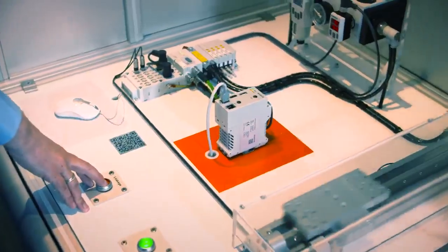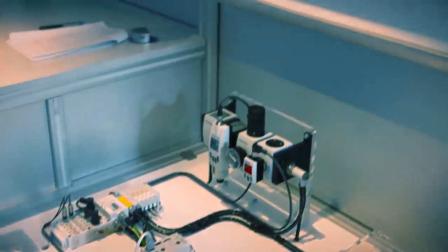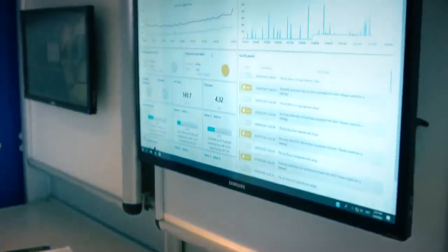If we detect an anomaly in the consumption per working cycle, that usually means that there is a developing leakage, and we can give a notification that this is currently happening, like we can show in our application by creating an artificial leakage.